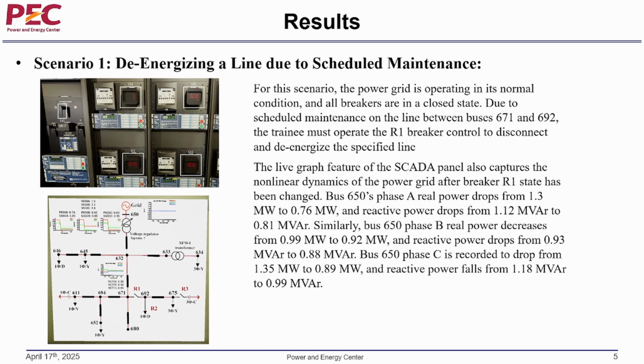The live graph feature of the SCADA panel also captures the nonlinear dynamic of the power grid after breaker R1 has been changed. This here shows the bus 650 three-phase power after breaker R1 had been disconnected. In phase A, the real power dropped from 1.3 megawatt to 0.76 megawatt. And for reactive power, similarly, the reactive power dropped from 1.12 megavar to 0.81 megavar. The same direction can be observed in phase B and phase C of bus 650.